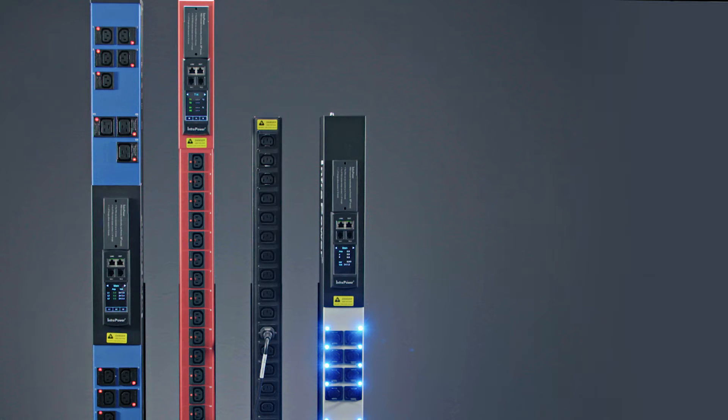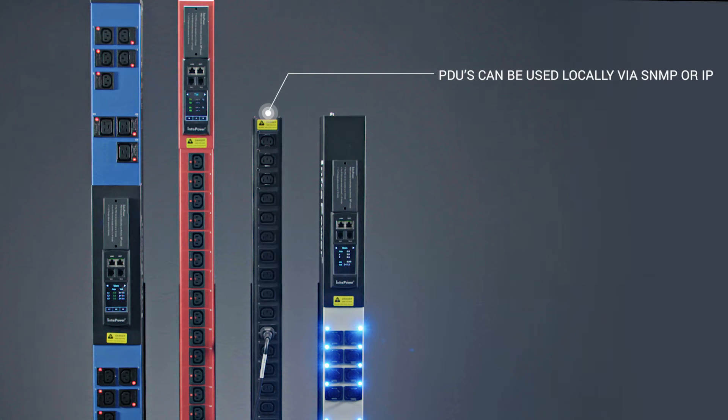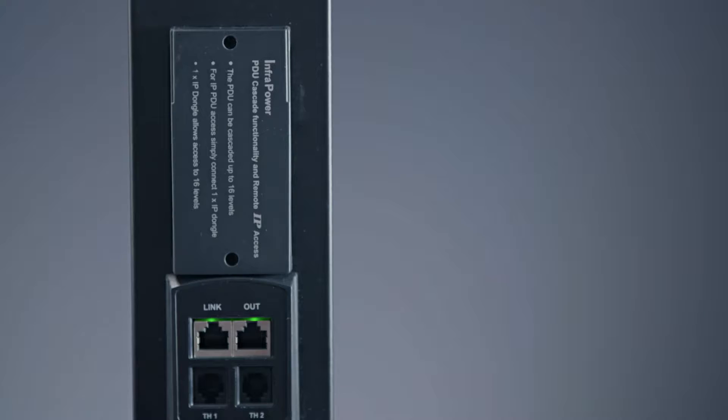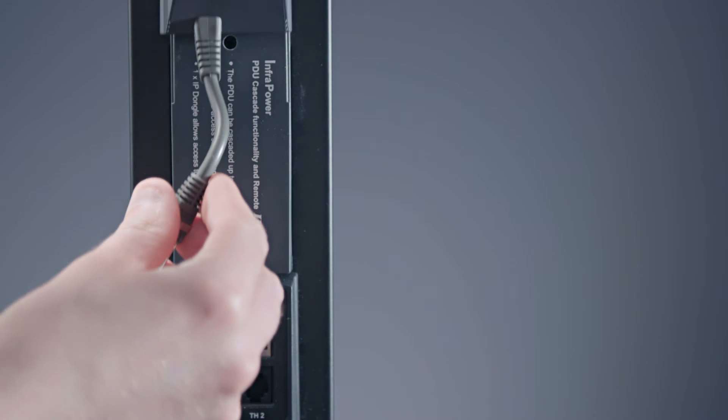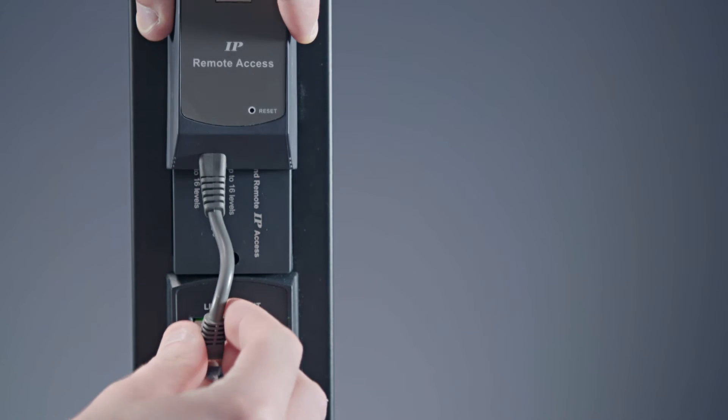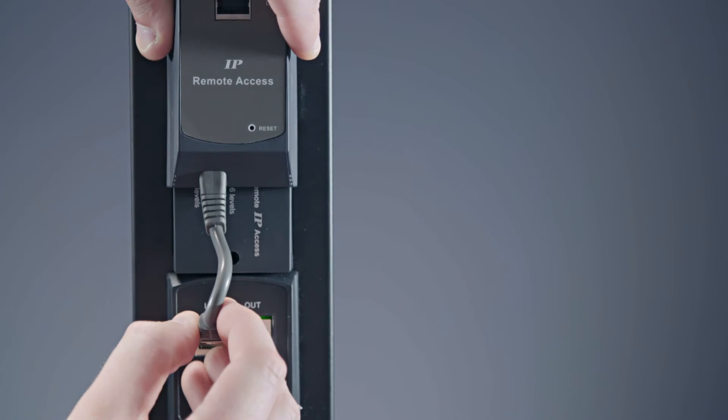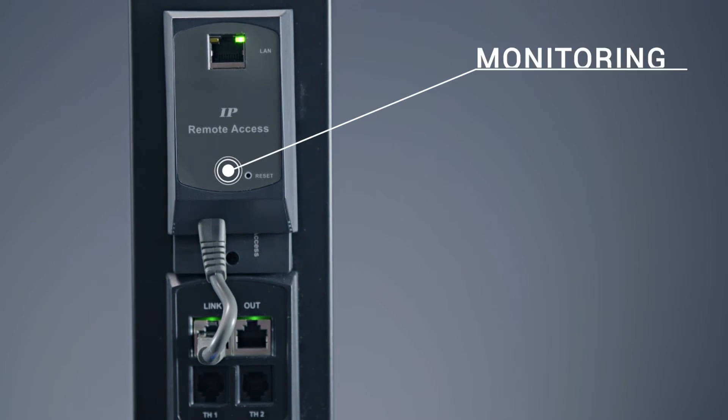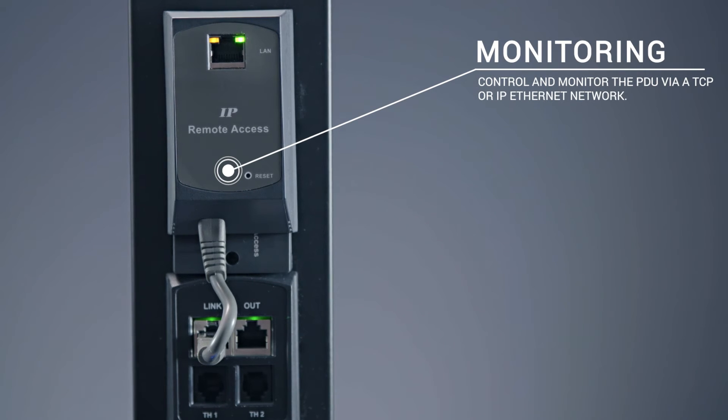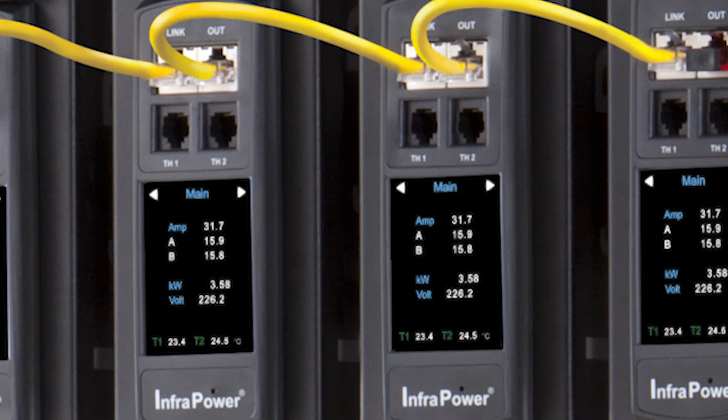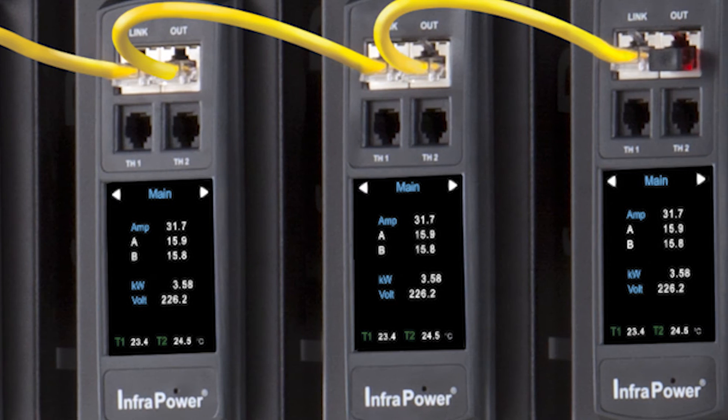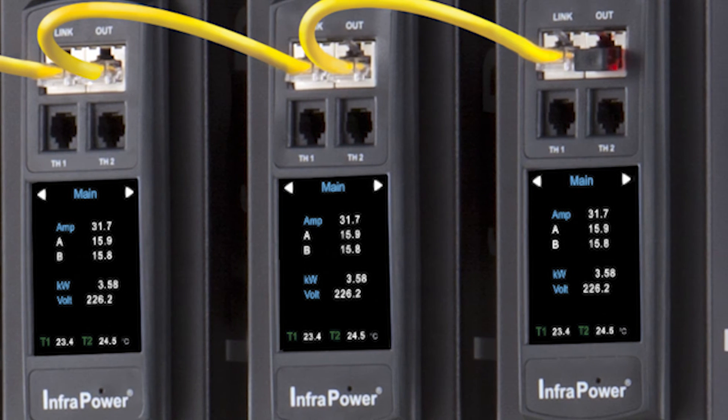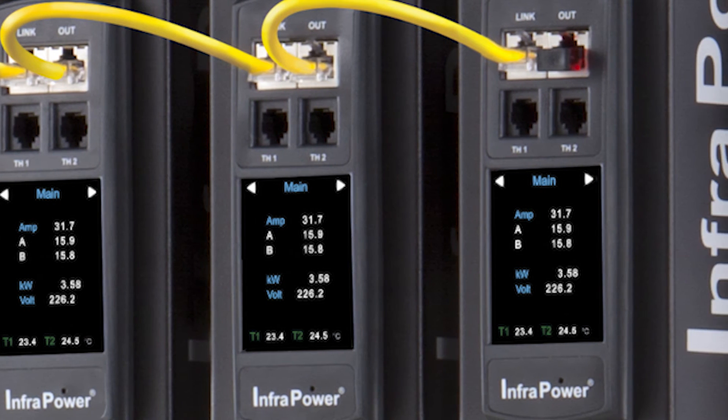InfraPower locally metered, remotely monitored and switched rack PDUs are designed for use across the network either locally via SNMP or over IP. PDUs are IP addressable over a TCP IP Ethernet network for remote control and monitoring via an IP dongle. One IP dongle allows access of up to 16 PDUs in a single daisy chain.